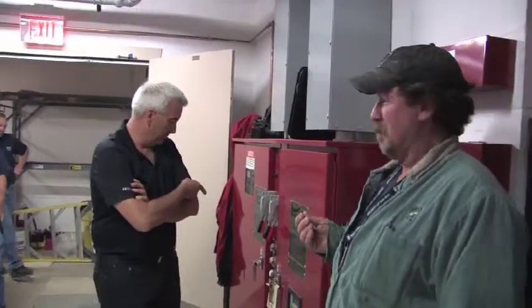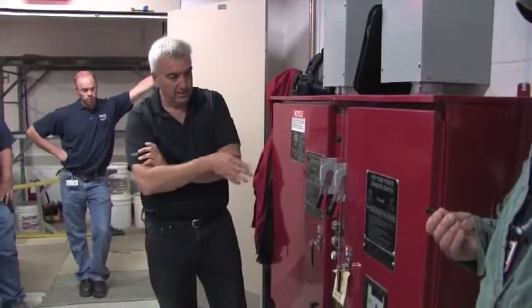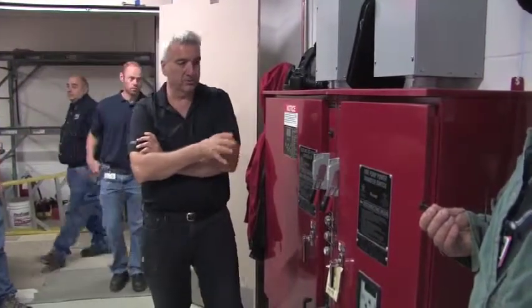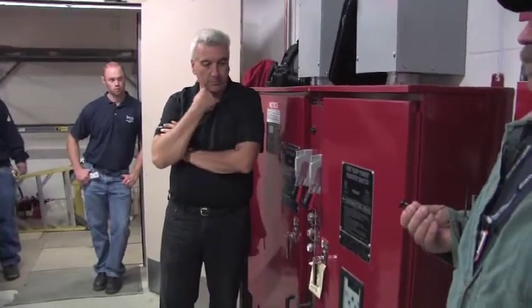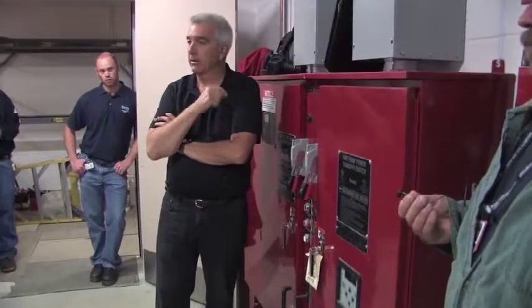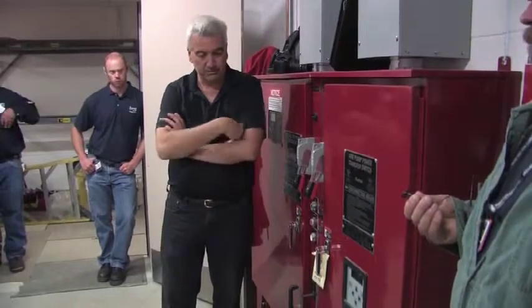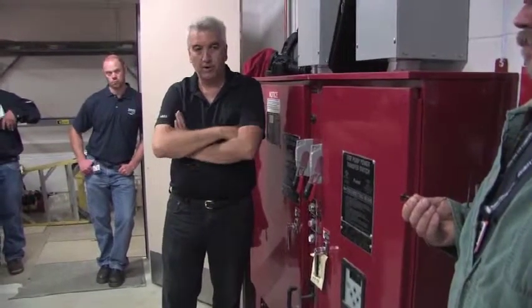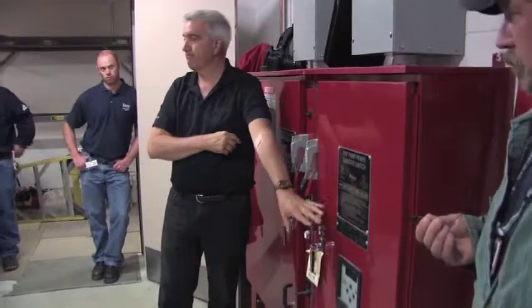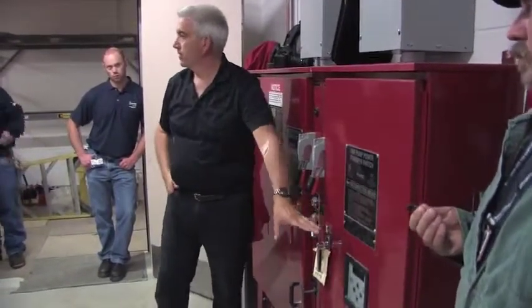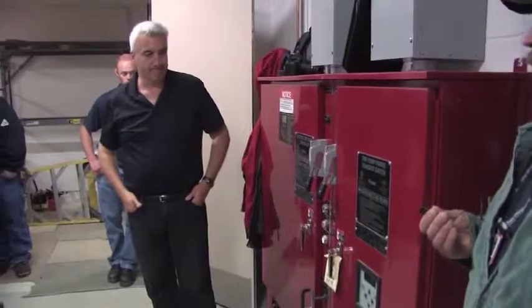This is a 1350, which is a wye-delta starter, and that one over there was a 1930, which is an electronic soft start and soft stop controller. So each of these controllers are equipped with an automatic transfer switch made by ASCO. In fact, ASCO owns Firetrol now. They've owned it for about 10 or so years, and we use the nice new ASCO control module that gives us all kinds of information from the generator as well now, which is kind of nice.